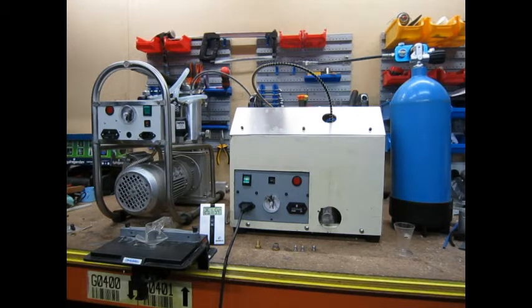That compressor features a dual cooling system with air cooling for the first stage and independent auxiliary liquid cooling for the second stage. This allows us to keep the working temperature of the second stage piston below 50 degrees Celsius or 122 degrees Fahrenheit.